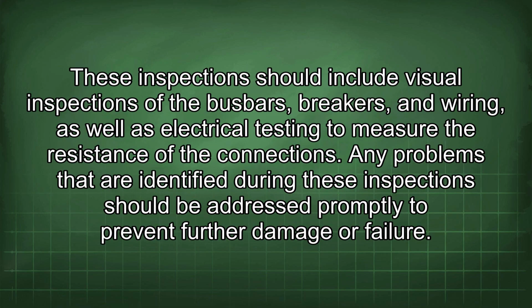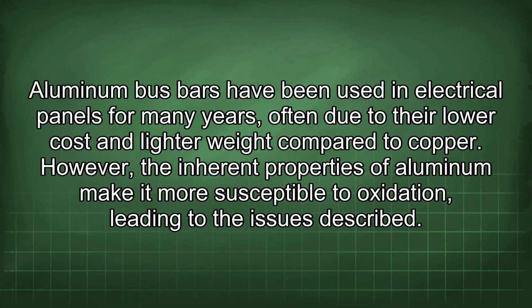These inspections should include visual inspections of the busbars, breakers, and wiring, as well as electrical testing to measure the resistance of the connections. Any problems that are identified during these inspections should be addressed promptly to prevent further damage or failure. Aluminum busbars have been used in electrical panels for many years, often due to their lower cost and lighter weight compared to copper.